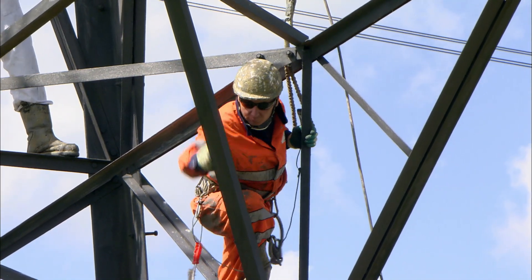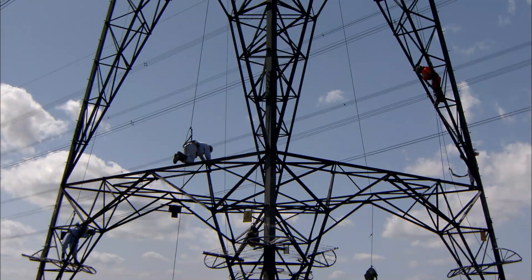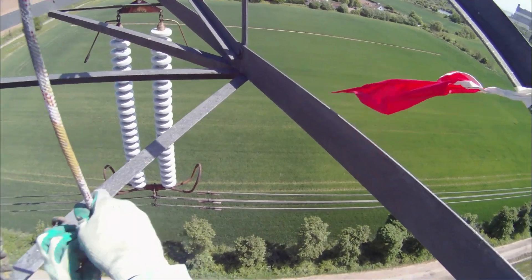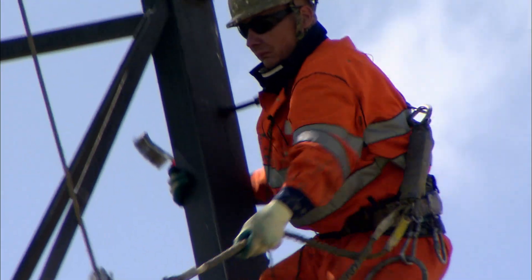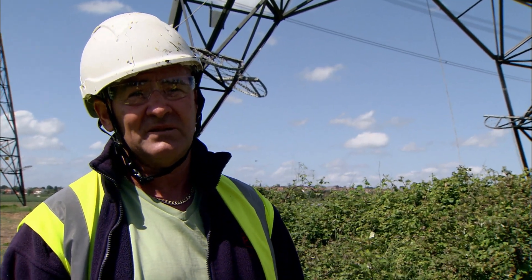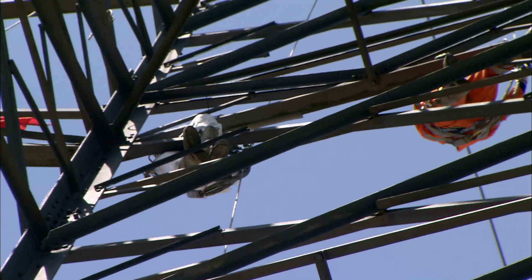While the men are on the steel towers, they have to be careful — the electricity is still on. This tower at the moment is live, so they can't go onto the arms; they can only work on the tower structure, the tower body. We've got red pennants up on the arms, demarcating the live area. The red flags mark the safe distance from the live 400,000 volt conductor: 3.1 metres. Any closer and there's a danger of arcing — electricity leaping from conductor to man like lightning. It can arc out at you, and you'll have serious burns. You'd probably be killed with 400,000 volts — you probably wouldn't survive. Sometimes when you're climbing up a tower body, as you're going past the cables carrying the power, you'll get little static electric shots. Makes you a bit jumpy, but they get used to that — it's part and parcel of the job.